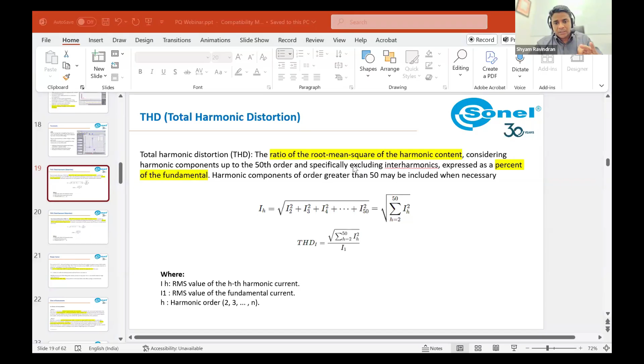Coming back to the fundamentals, THD and TDD. The only difference here is the denominator is not the instantaneous value. The denominator for the new regulation is actually the maximum value. So 100 divided by 10 can be 10, but 100 divided by 50 can be 2. So I have to emphasize always on having the highest denominator value. Most customers do not have the data of their IL value, but we can find it out.